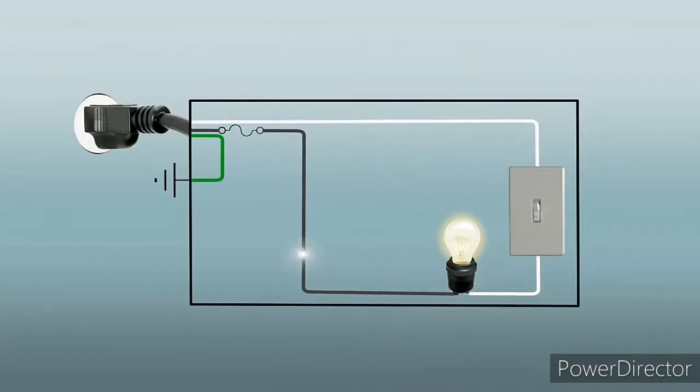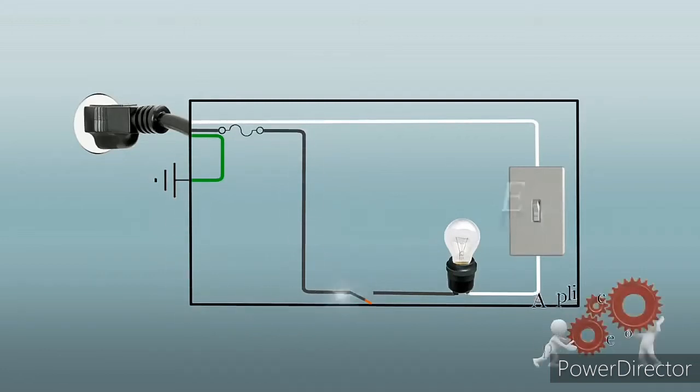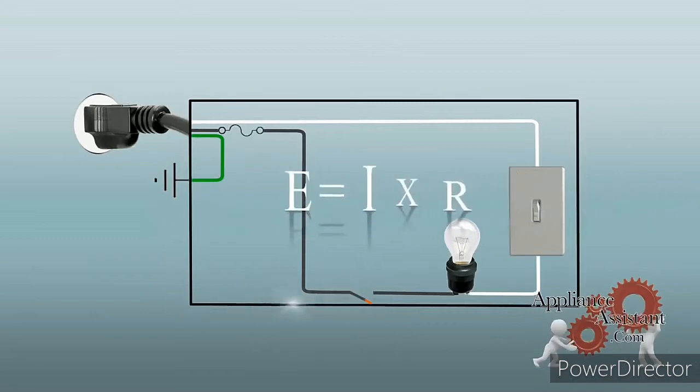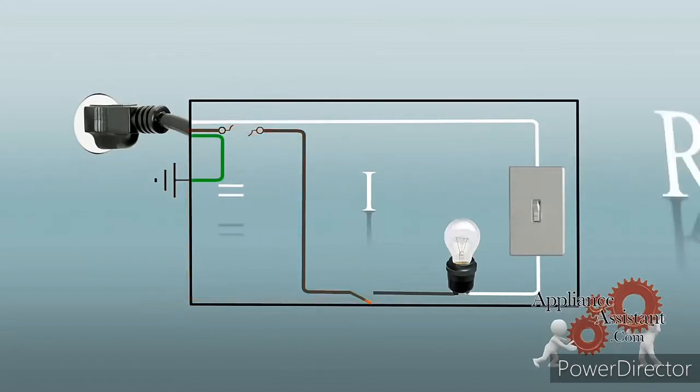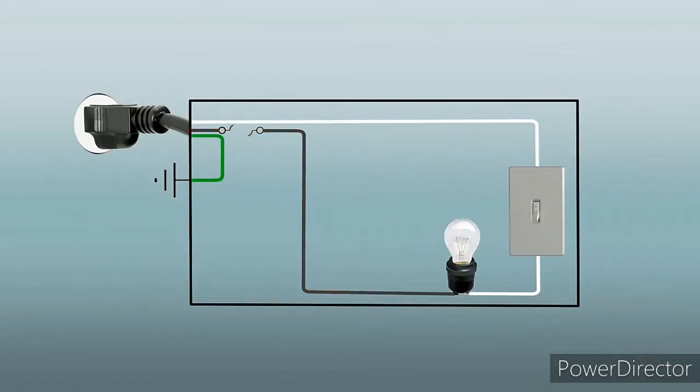A grounded circuit happens when a hot wire comes into contact with the cabinet or grounded part. When this happens, the circuit is again shunted to a neutral connection, in this case ground. The load is bypassed, the resistance decreased, the amperage increased, and you know the rest. See, it's pretty simple. We locate the problem, fix it, reset the breaker, or replace the fuse, and bingo, you're back in business. Lastly, an open circuit.